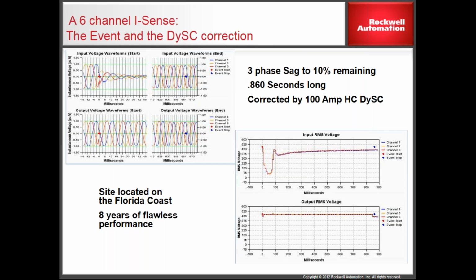And when we look at the RMS values over here on the right, what we see is this was catastrophic in the first 50 milliseconds. All 3 phases dropped almost to about 10% remaining, not quite 0. Then they came up, except they didn't quite make it. And then it kind of dinked around for almost a second before it finally got up over 90%. So the DySC turned on here, when the output RMS values.